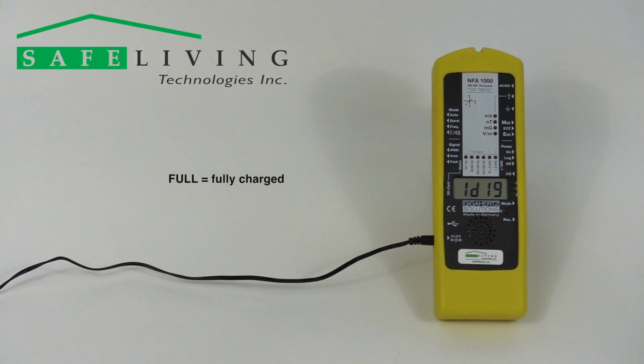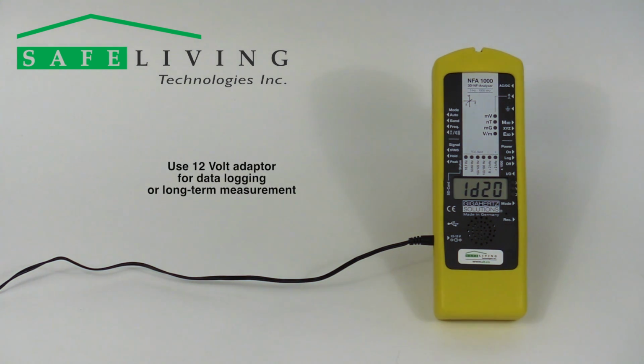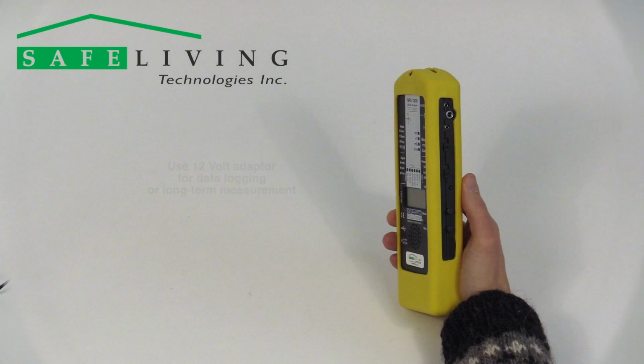If you see full on the display, it's time to unplug the charger from the meter. Note that an older battery may not reach the indicated full display status, but will still be acceptable to use. The 12-volt AC adapter is only used to power the meter for long-term data collection and measurement. It will not charge the meter.